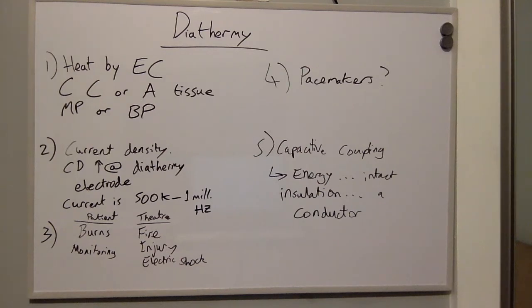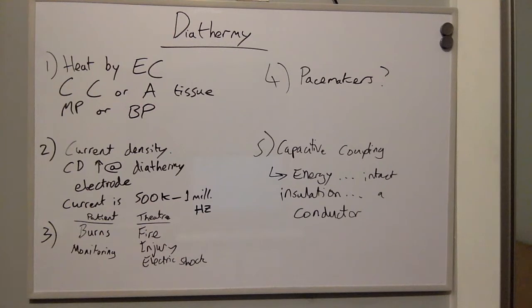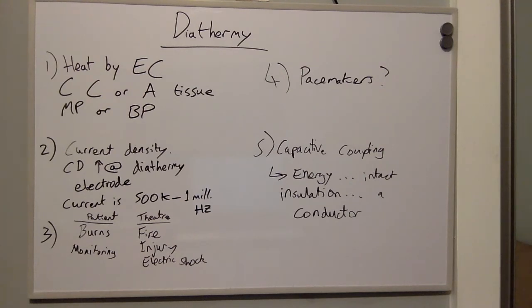There are potential dangers involved with the use of diathermy. For the patient, this can include burns, damage to deep underlying structures, and interference with monitoring. For theatre and theatre staff, this can include the starting of a fire by ignition of flammable materials, injury and burns to theatre staff, and electric shock.